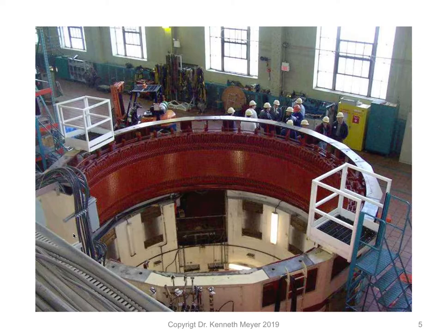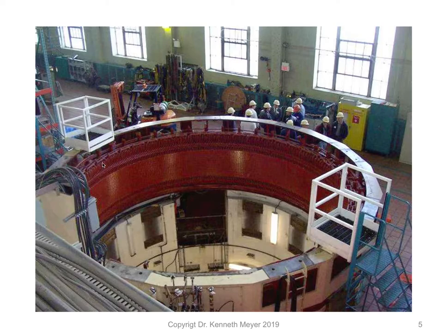Here's a real stator. You can see around where the cursor is — these are the actual windings. Instead of just three, there are probably closer to 300 windings around the machine. Once they're all connected in their appropriate series-parallel arrangements — you can see connections at the top and bottom — you effectively end up with three phases all at 120 degrees from each other. That's how an actual stator looks, in this case a hydropower station turbine stator.